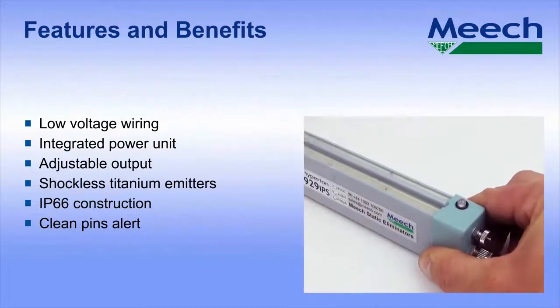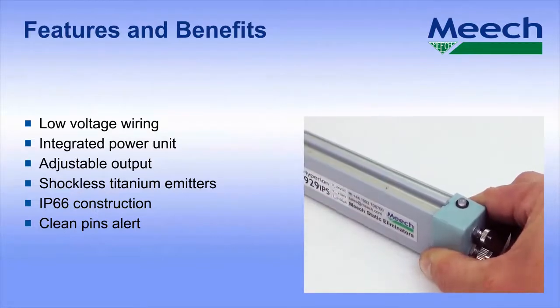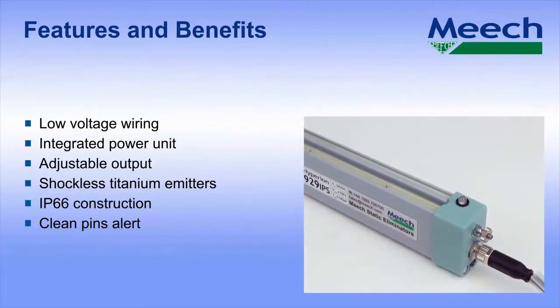A red flashing LED shows that the Meech's ion current monitoring technology has detected that the bar needs cleaning. Vital information not available on competitors' bars. Constant red illumination indicates that a fault has been detected on the high voltage outputs.